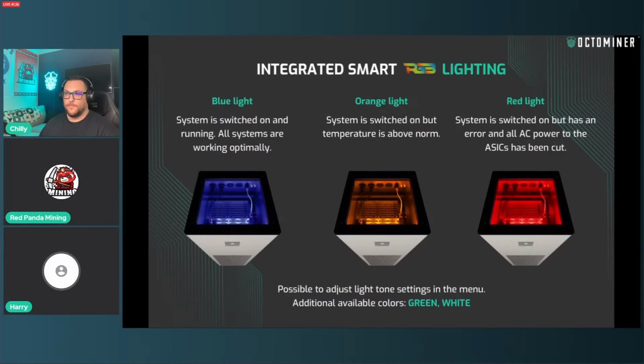And then if anything is out of the norm - meaning temperature isn't just a little over, it's not just the orange lighting level, temperature goes too high for some reason, or something else - then the system will cut the AC power to the ASIC units. The miners get no power, they're fully shut off. The system will also shut off the pumps and fans, and the red light goes on, meaning some kind of fault has been detected, and the user would need to inspect the system.